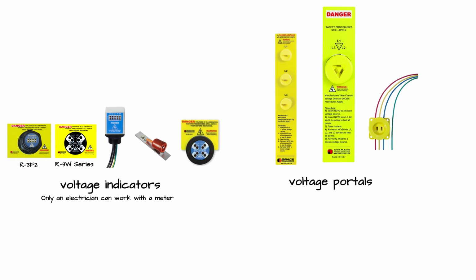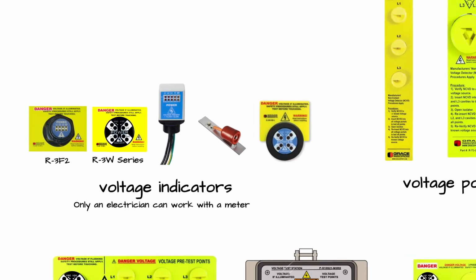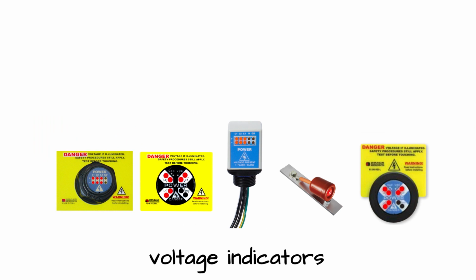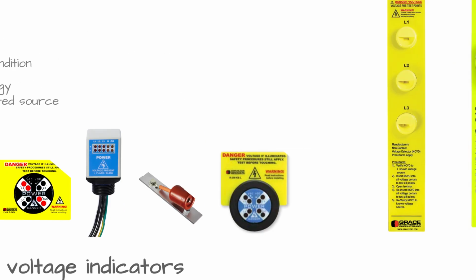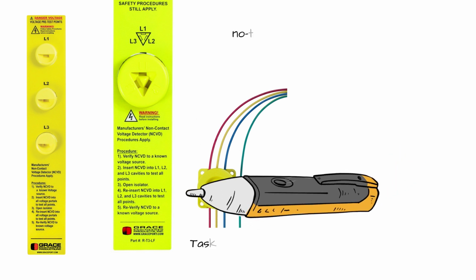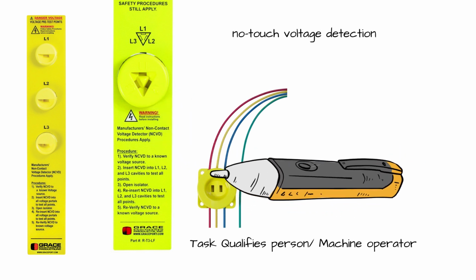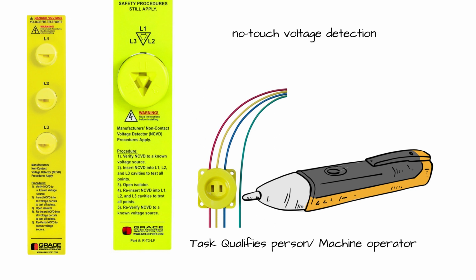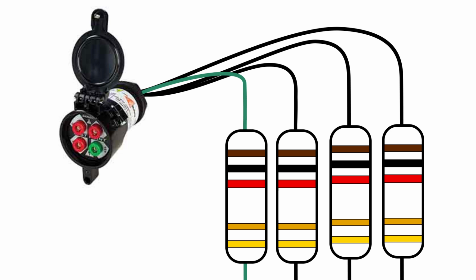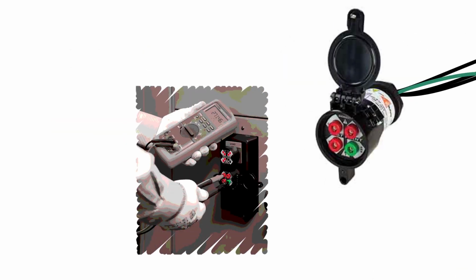Grace's PESDs consist of voltage indicators, voltage portals, and combination units of the two. Our voltage indicators visually represent the presence of voltage with flashing or non-flashing redundant LED lights. In addition, these indicators also show the lost phase, stuck blade condition, and dissipated energy of the connected source. The voltage portals offer the maintenance personnel a no-touch voltage detection using an NCVD pen on the outside of a grounded electrical cabinet. On the other hand, a safe test point portal with a 102 kiloohm high impedance protected circuit offers the qualified person the ability to perform the absence of voltage test from outside the cabinet without opening the door.